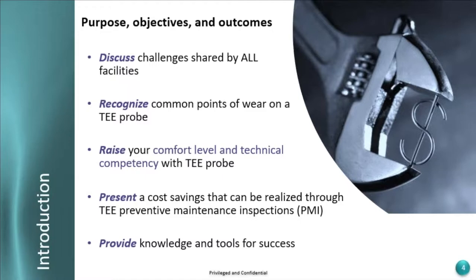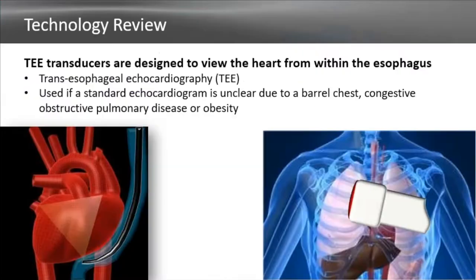We offer preventative maintenance on these transesophageal probes, where we will proactively, and we can do this overnight, you send it in and we can replace the bending rubber, the locking collars, the glue beads, and we'll take a look. We'll do a full examination of the probe itself, adjust the articulation, and it's extremely low cost compared to what a major TEE repair would cost you.